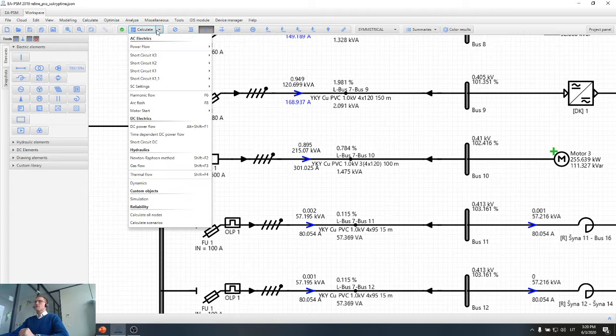So basically, our protection device should not trip during this kind of normal mode. The next calculation that we need for protection coordination is different types of short circuits. For example, if we do ground fault protection, we need information about one-phase short circuits, and because ground fault protection measures zero sequence currents, we need information especially about the zero sequence currents in the electrical network in case of a one-phase short circuit. Then there are three-phase and two-phase short circuits, which are again needed for different cases. Two-phase short circuit is needed for setting protection devices, and three-phase short circuit is needed for equipment selection, like busbar selection, and also breaker capability selection, because we need to make sure that the breaker will be capable of disconnecting short circuit current even in the maximum, worst case scenario.